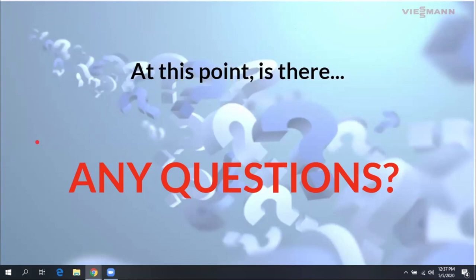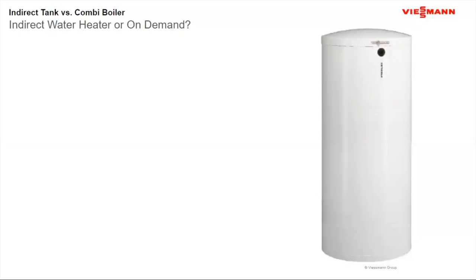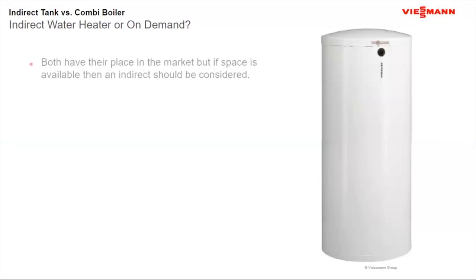So from a sizing standpoint, you can see that there is a difference in the sizing process. And generally, when I look at combi boilers for anything besides a small house, the boiler size a lot of times has to grow to support the combi because it doesn't have any storage. And as you saw there, the boiler potentially will grow to be at least twice as large as what was needed with the properly sized boiler with the indirect storage water heater. But when we compare the two, there are a lot of other things that are different from a performance standpoint, and again, in my thinking, that tends to skew the table in the direction of the indirect water heater.